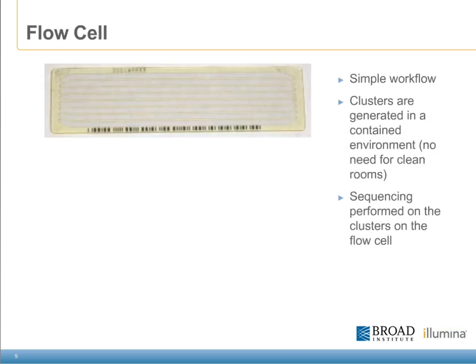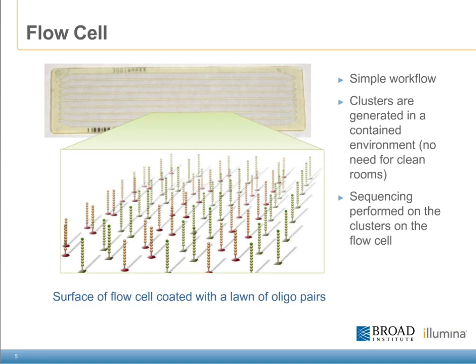This is a close-up image of a flow cell for a genome analyzer. You can see eight lanes, eight channels, each with a port on the far right and far left side for fluid to flow through. The flow cell is a little bit like a glass sandwich with channels running through it. The entire top surface is glass with the port openings, the bottom surface is solid glass, and it has lane lines in between to prevent any cross-contamination between samples.